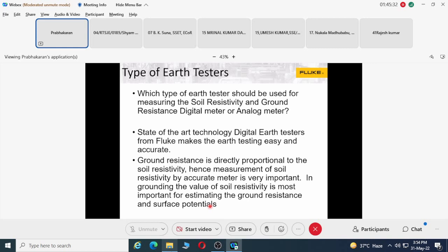State of the art digital testers are used for accurate measurement. You can use a digital tester or an analog tester, but each has its own advantages and disadvantages. Ground resistance is directly proportional to the soil resistivity.